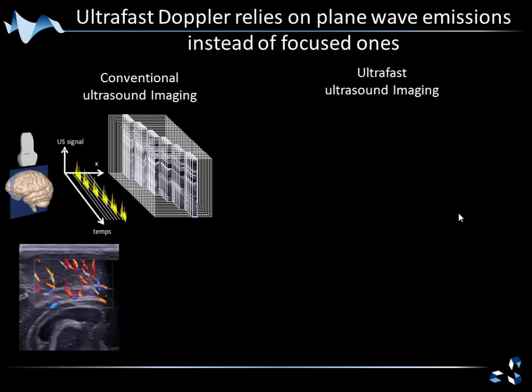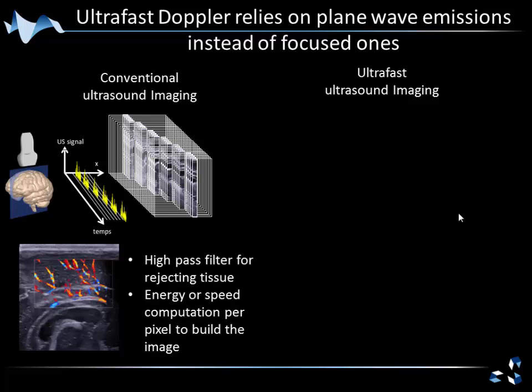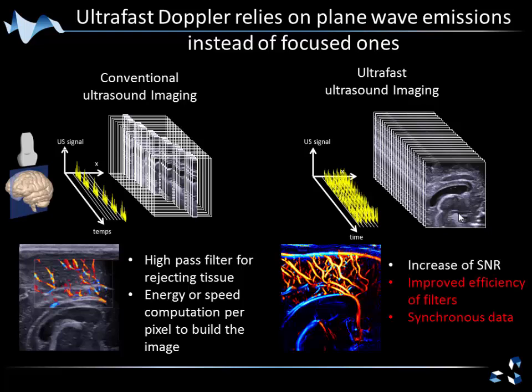This change implies a lot for Doppler imaging. In conventional Doppler, you collect a few samples per location and move to the next, so you have only a few samples per pixel. This is enough to detect large blood flow, but not very sensitive. In ultra-fast imaging, you build images continuously, so virtually you could have an infinite number of samples in every location, which increases the signal-to-noise ratio.